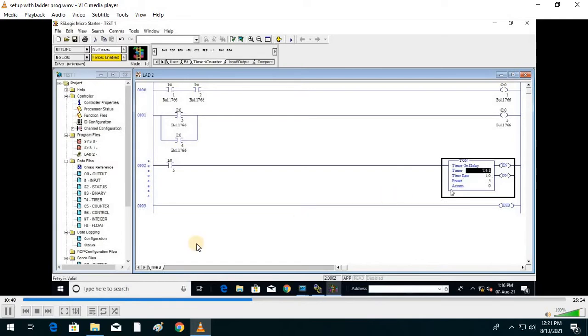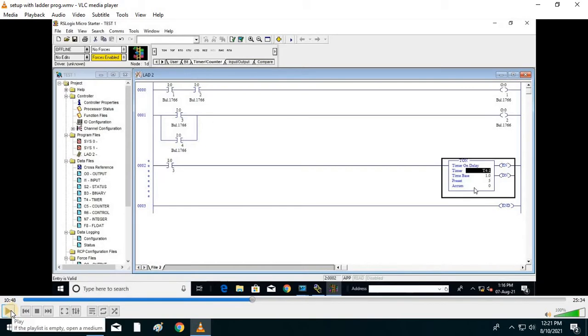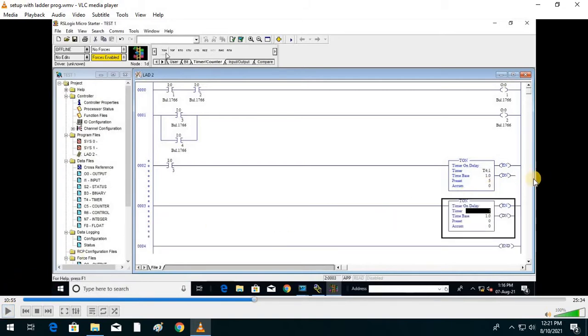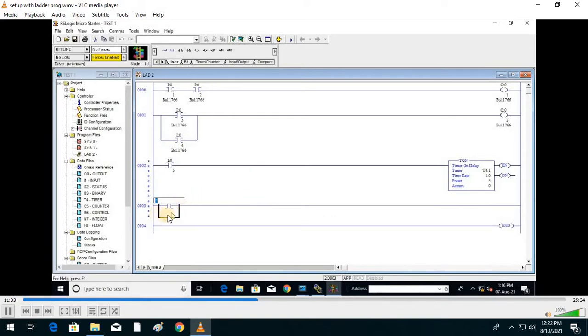Go to the Preset value — preset is the value in seconds after which your timer will turn on. In the virtual lab preset was in milliseconds, but here it is in seconds. Preset value is set to 5. There are two bits: the enable bit and the done bit. To check the done bit indication, add an examine-if-closed contact and put the name slash DN bit.